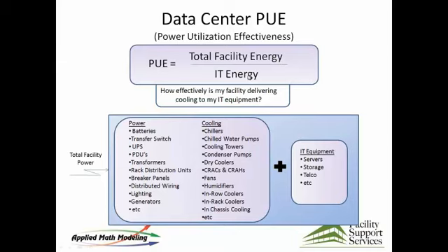Now, it doesn't mean that that air all gets to the right place, and that's a lot of what we'll be talking about today. But at least knowing what this ratio is very important for you because it gives you a feel for understanding how much cooling you have, if you have too much cooling, etc. The other metric we'll be using today is called RCI. This is another metric that looks at conformance of the ASHRAE specification for rack inlet temperature. How well are the racks in your particular data center conforming to this standard? And here we're looking at a Class I standard of 64 to 80 Fahrenheit recommended, or 59 to roughly 90 allowable.